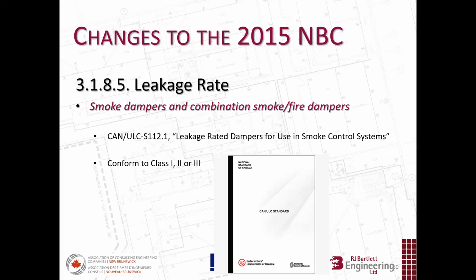In there, it says the leakage rating can be class 1, 2, or 3. A case study I can share with you is we had the question asked to us about a hospital in the Atlantic province. And they said, what kind of leakage rating class do I need to have for my smoke dampers, which are in a hospital? Can they just be whichever? What we found is it appears they can be just class 1, 2, or 3, but when doing some further investigating, the IBC, which is the International Building Code in the States, does actually specify that for health and care occupancies, they want you to have a minimum of class 2.